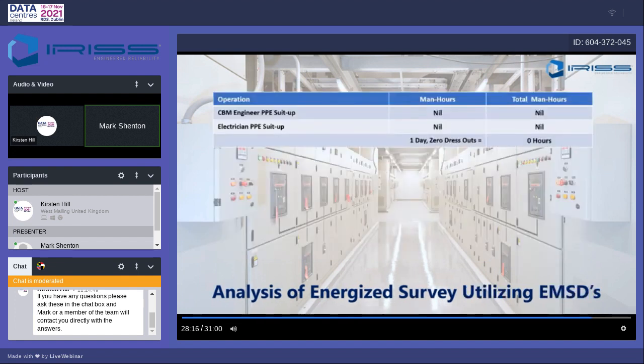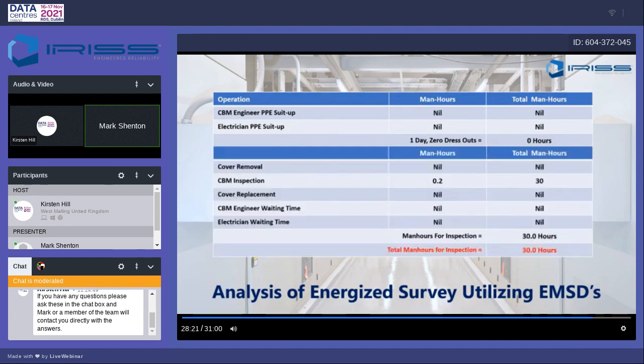Once the EMSDs was in, because there's no need to shut down, no need for PPE, no cover removal or replacement, the CBM inspection actually increased to 30 hours, but that included writing the report. In fact, in this area we did the whole inspection in 7 hours, but added the additional hours for report generation, upload to the CMMS, work orders, that type of thing.